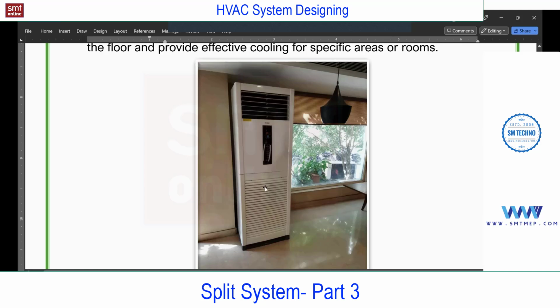So if you talk about advantages, for example, in this case, this wall is completely glass, so there is no option for a high wall. Similarly, you will not get the clearance on the wall. In that case, we can think of this. Or else, most commonly in actual practice, if the client decides to go for AC after completing the interior works, in that case you can suggest this option.